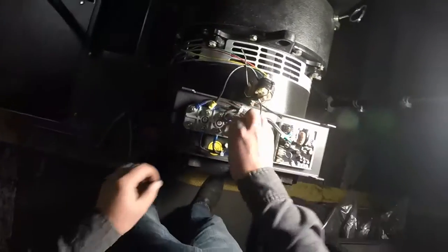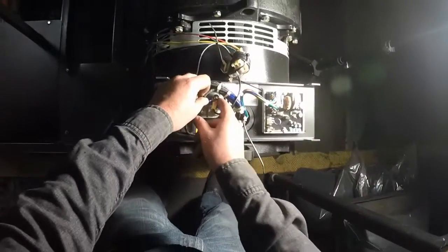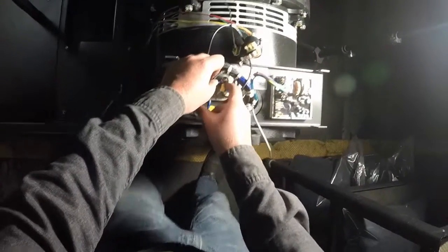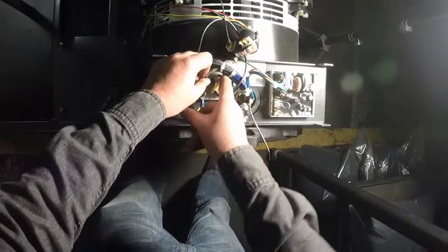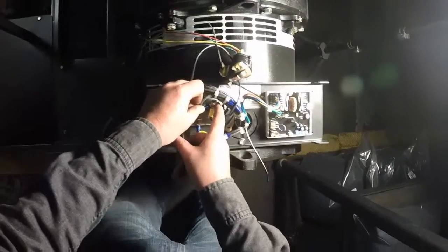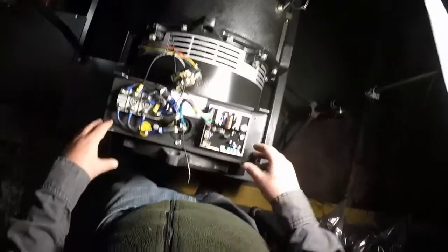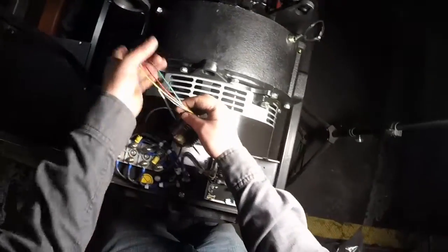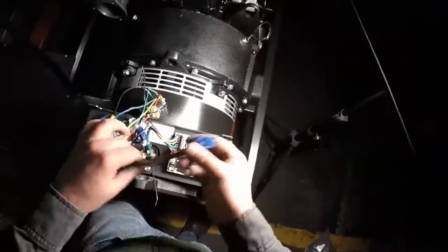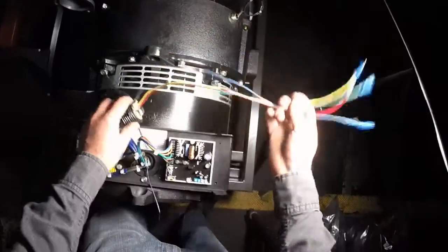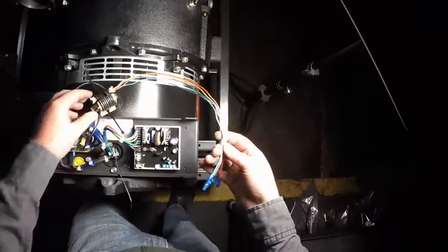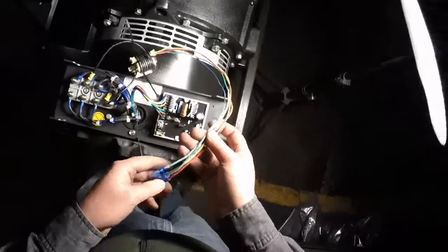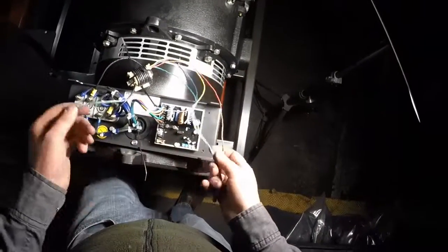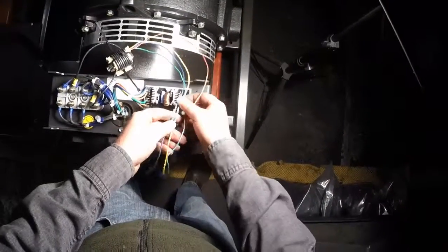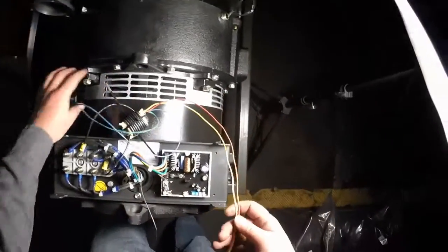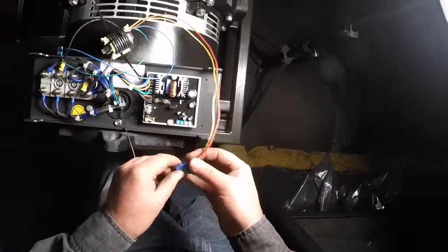Okay, so now we have the wiring to allow the current flow set up on the generator. The other part that we need to connect are the wires that come out of the generator, or out of the current transformer, and these are used to create a biased input signal to the AVR.